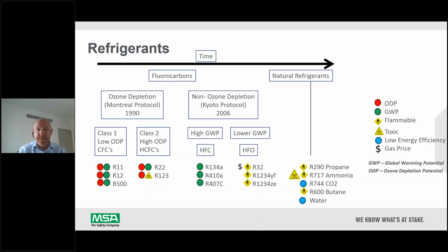refrigerants globally still. These were highly global warming, so the Kyoto Protocol was signed in 2006 in order to start to phase out these. And then we have more recently had the Kigali Agreement in order to phase these out globally. So the newer refrigerants are the lower GWP refrigerants, the HFOs, and then we can see the more natural refrigerants actually coming back into use much more. Propane, ammonia, and carbon dioxide are being used as gases in refrigeration systems more often because they're naturally occurring.